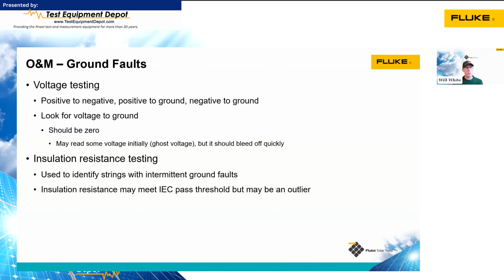So an example, I was doing testing on a roof-mounted commercial system. This was a low slope, essentially a flat commercial roof. Doing insulation resistance testing, every string was exceeding the maximum of my meter, which was 2 giga-ohms, except for one string. And the one string had like 156 mega-ohms or something. According to the standard, that was a passing test. The IEC standard calls for 1 mega ohm minimum resistance to be passing.